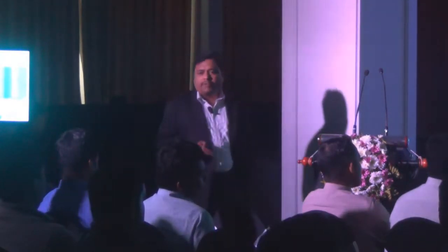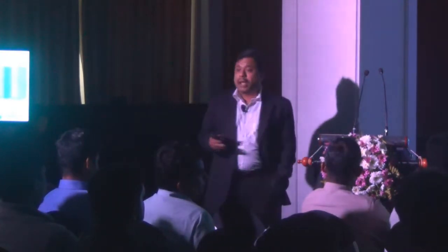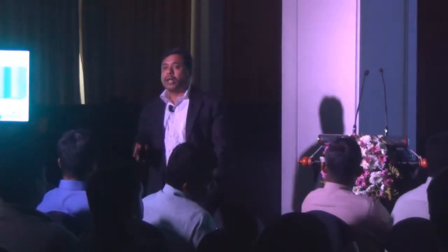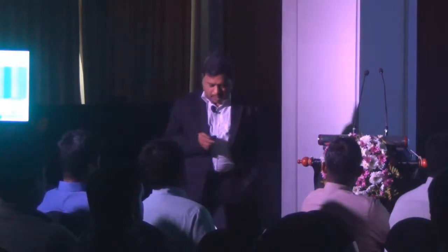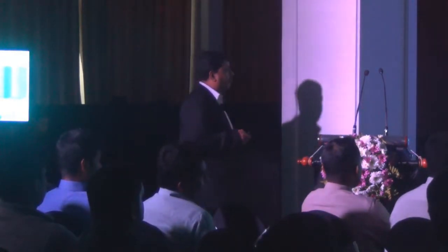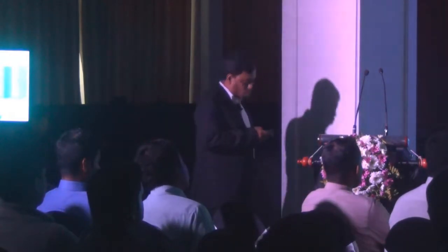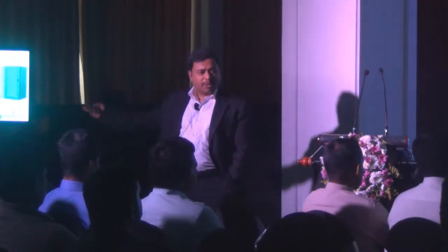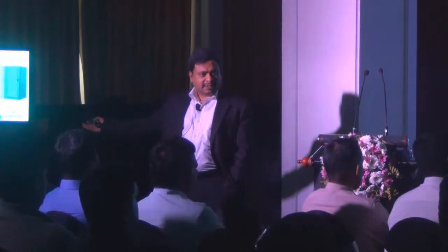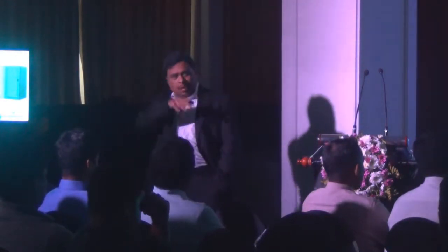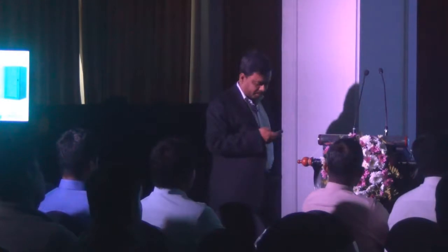What we achieve by doing this is simple. We can have a very high efficiency on all your UPS systems, where you can save power heavily. The overall efficiency will increase, and you can also select the module you want. This can be programmed according to the site condition. Suppose UPS module 1 can be kept in sleep mode at the beginning, then the UPS 4 module can be kept in sleep mode for a second. Like that we can program however the customer prefers.